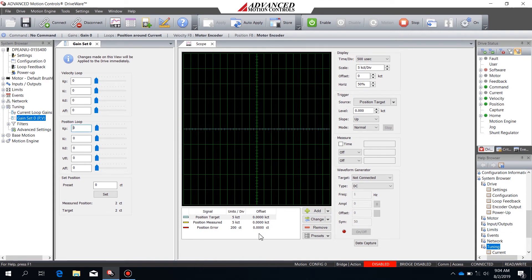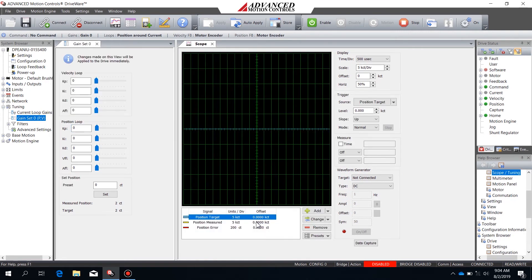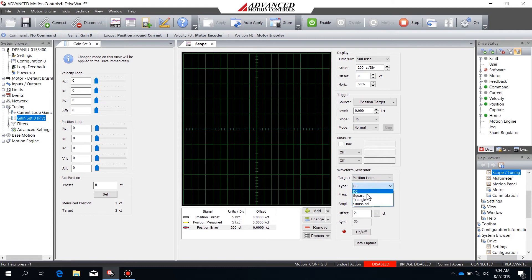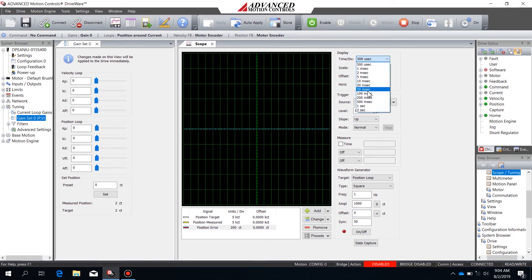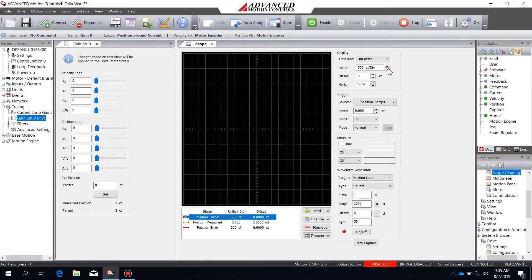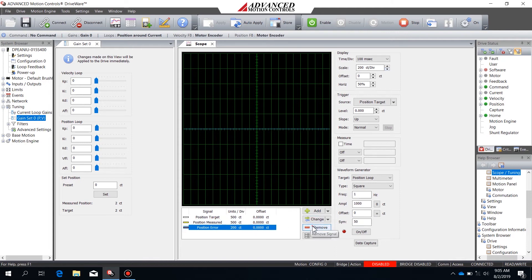I'll then open gain set zero along with the DriveWare oscilloscope to begin tuning. My presets are already in position, so I don't need to change them. I'm going to change the waveform target to position loop, this time with a square wave. I'll leave the frequency at one hertz, zero out the offset, and set the amplitude to a much smaller value of 1,000 counts — in my case a tenth of a revolution. I'll reduce the time per division and scaling so everything stays on screen, and remove position error to avoid cluttering the screen since I'm not concerned about tight tolerances yet.